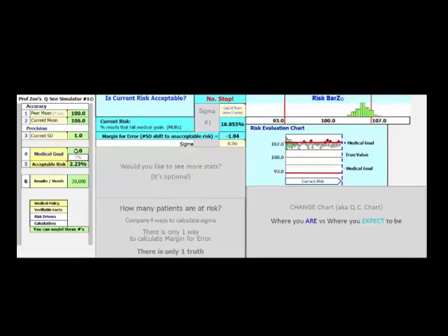The same method that is acceptable on the north side of the street is unacceptable on the south side of the street, because when you set your medical goal based on the biological variation limits, this is now a method with a sigma of only 1. The margin for error is -1, and 16% of your results are already failing, if you believe in biological variation. However, if you bring in a new clinical chemist and they believe in CLIA instead, then you're perfectly fine.